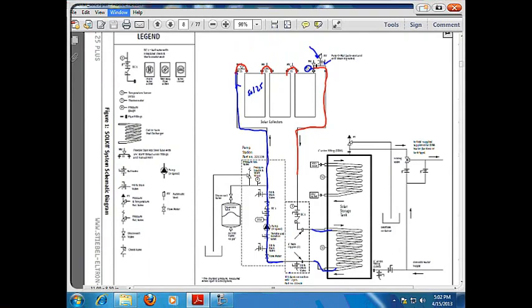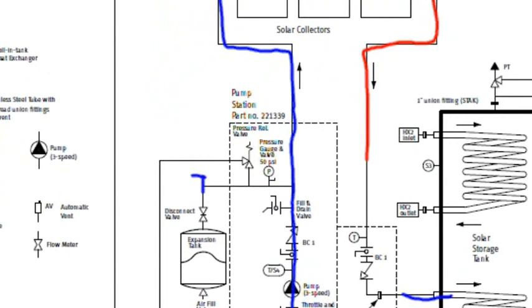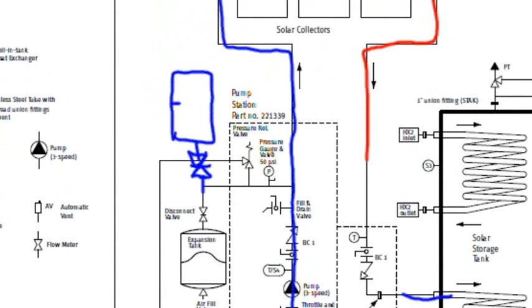A couple rules of the road. Some people like to put their expansion tank on the bottom. Another person likes to keep these up top. And the reason for keeping the expansion tank up top, as I'm drawing this, is if that bladder inside of that rubber bladder ever goes bad, I'm always going to be able to push fluid up and keep that air inside of that tank.